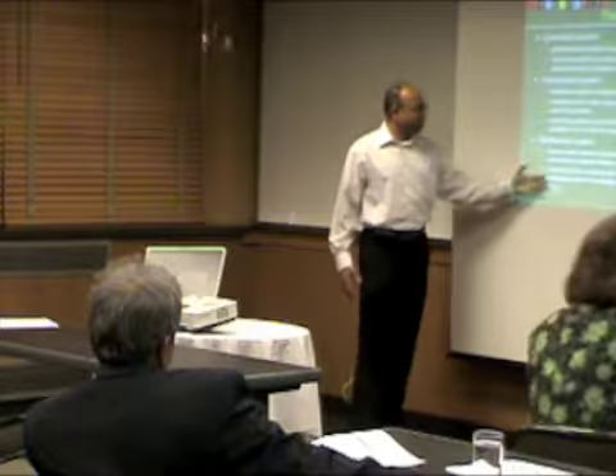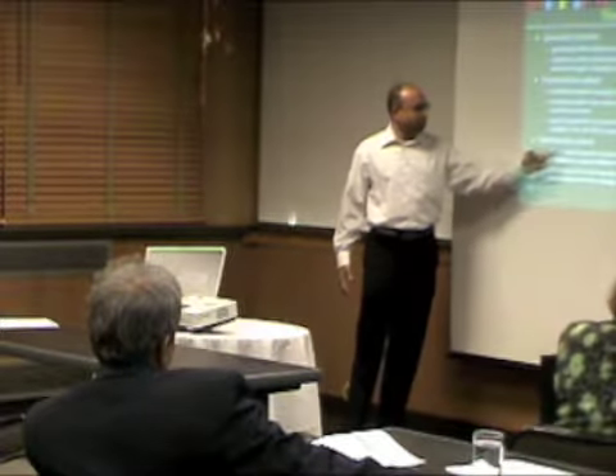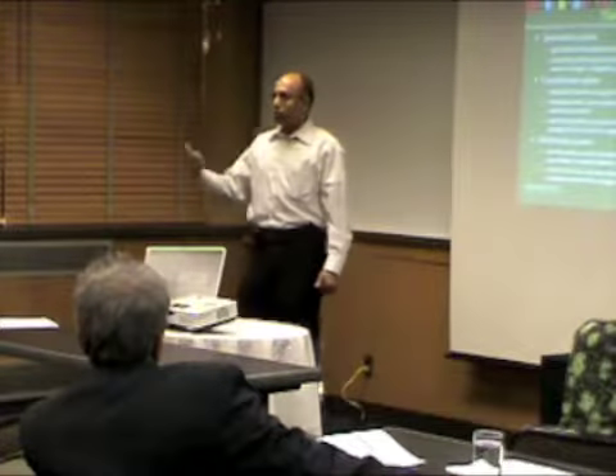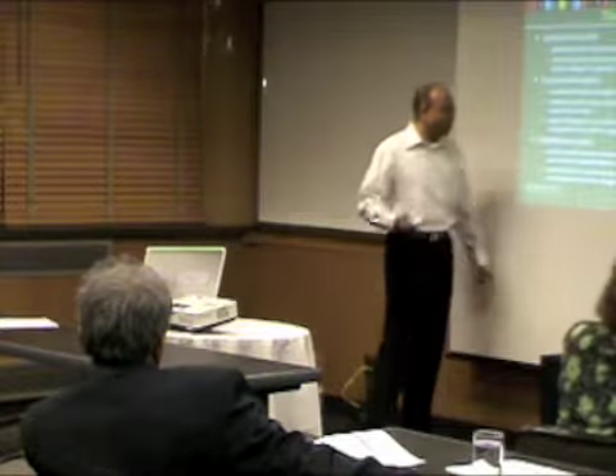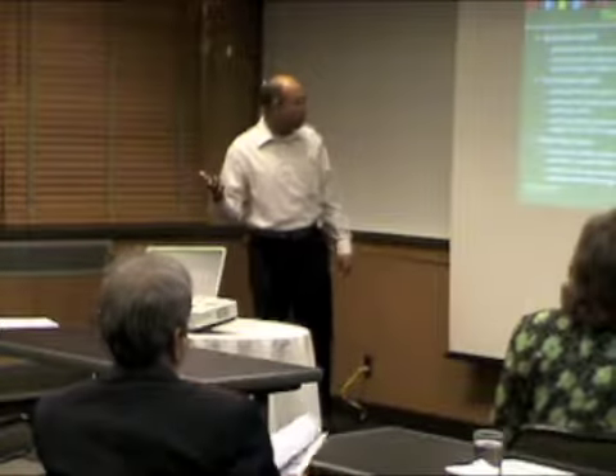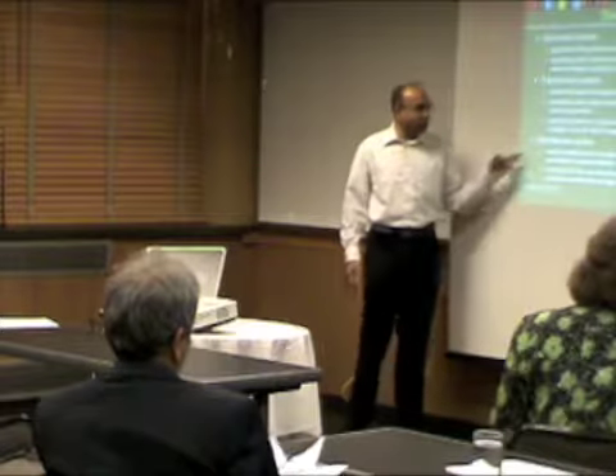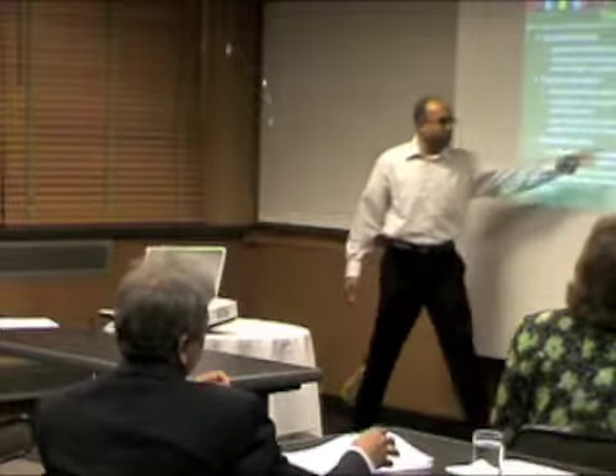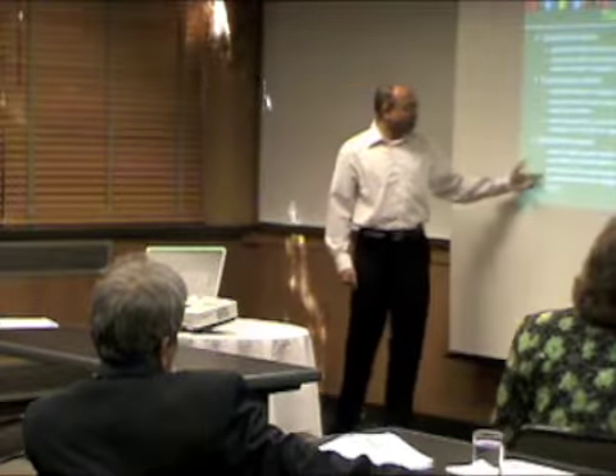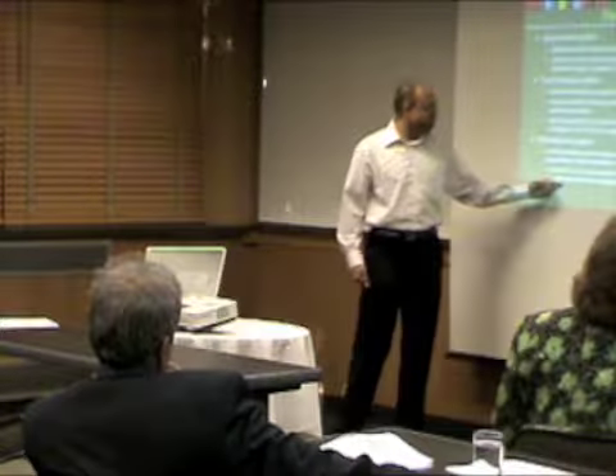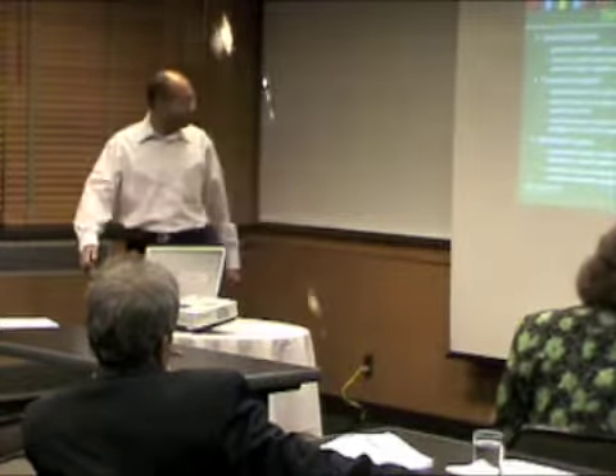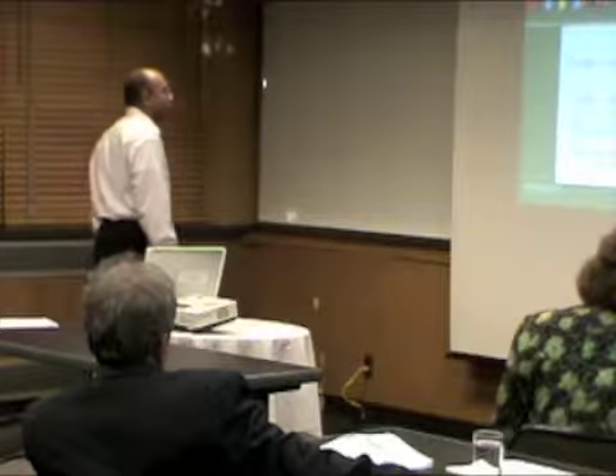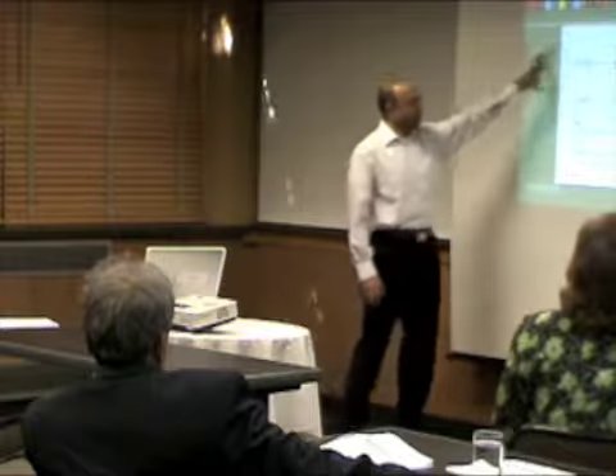And then the third part is the distribution system, which is mostly radial in nature, which means the power flows out in one direction through the feeders. There are no loops. There are some distribution systems with loops. Very dense urban distribution systems sometimes have loops, but most distribution systems in the United States do not. Okay? Through primary, that is three-phase, or secondary, that's single-phase feeders to customers. And the distribution system connects to the sub-transmission system through the distribution substation, where the voltage is stepped down to 33 kV and below. So here's a figure I drew to sort of mark out the boundaries.